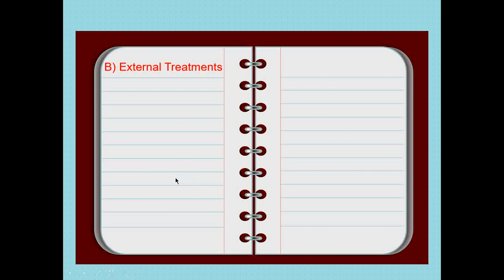Here in the first few slides we discussed the internal treatment, meaning when the water is taken into the boiler, then we can't filter it or apply other external treatments, but we can add some chemicals, and internally we can convert hard water into soft water. Now the time is of external treatment. Before entering water into the boiler, some treatments are carried out on water. Let us find out. The first external treatment is the zeolite or permutit method.